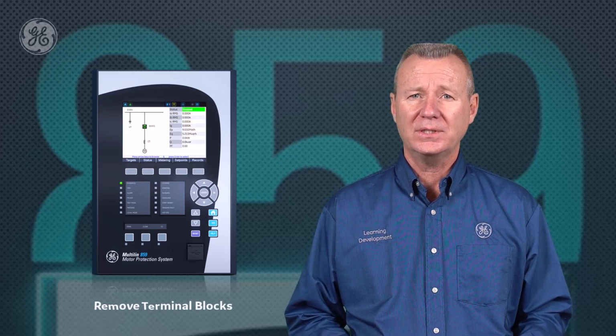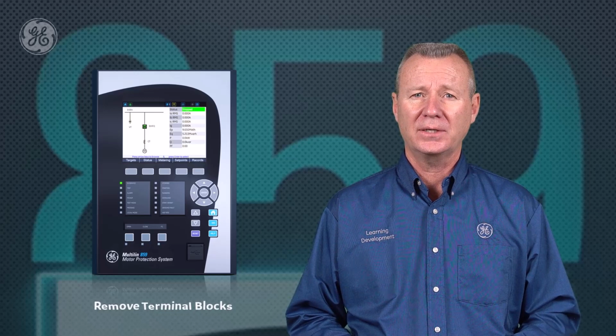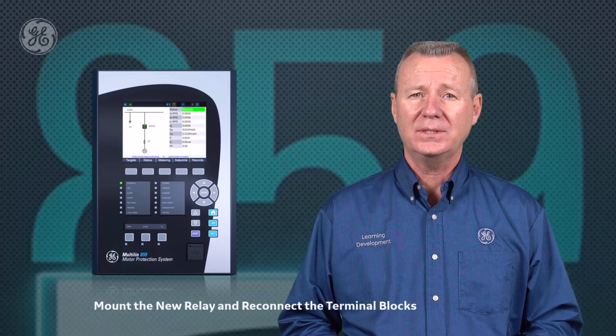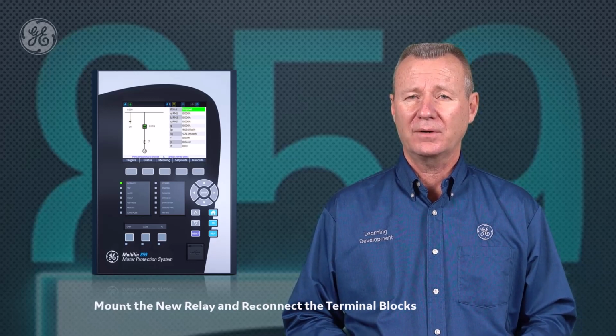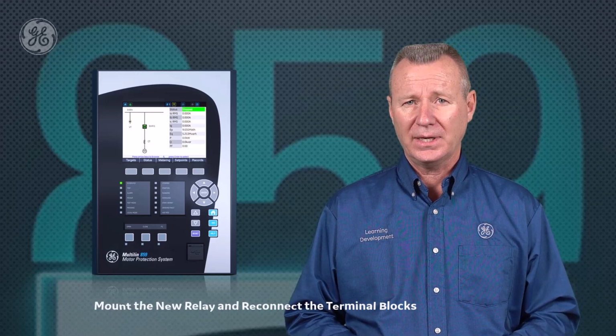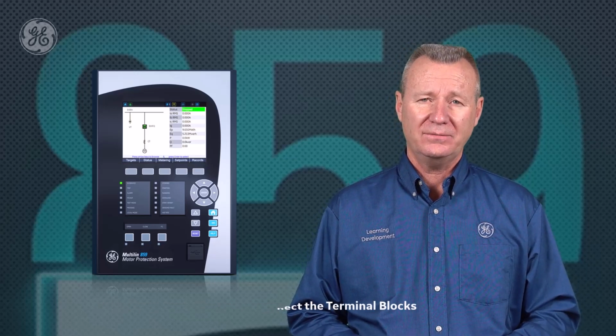For the relay outputs and CT-VT inputs of the 369, 269, and 269 Plus, these wires will need to be removed. Third, once step 2 is completed, we can mount the new 859 protection relay in our rack, plug in the RTD, digital input, and communication port terminals of the 369 into the 859 relay, and reconnect the relay's outputs and CT-VT wires. If you're upgrading from a 269 or a 269 Plus, it will be necessary to remove and reinstall all the wires to complete the upgrade. So now that we've outlined how this upgrade is going to work, let's move over to our rack so our instructor can walk you through the process step by step.